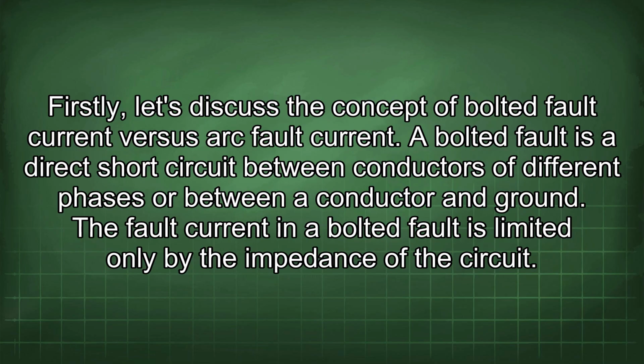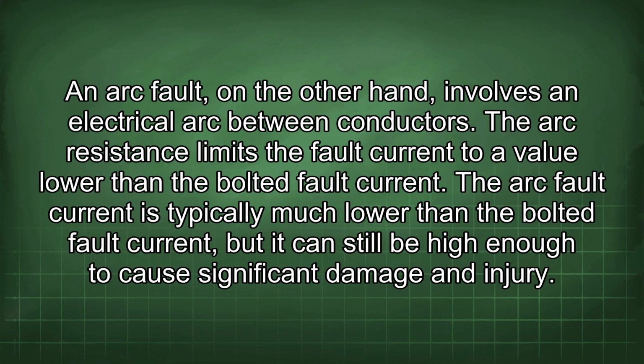Firstly, let's discuss the concept of bolted fault current versus arc fault current. A bolted fault is a direct short circuit between conductors of different phases or between a conductor and ground. The fault current in a bolted fault is limited only by the impedance of the circuit. An arc fault, on the other hand, involves an electrical arc between conductors. The arc resistance limits the fault current to a value lower than the bolted fault current. The arc fault current is typically much lower than the bolted fault current, but it can still be high enough to cause significant damage and injury.